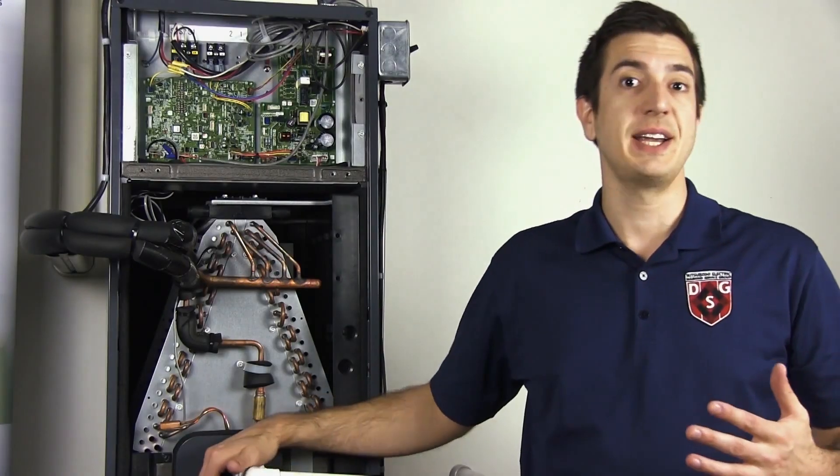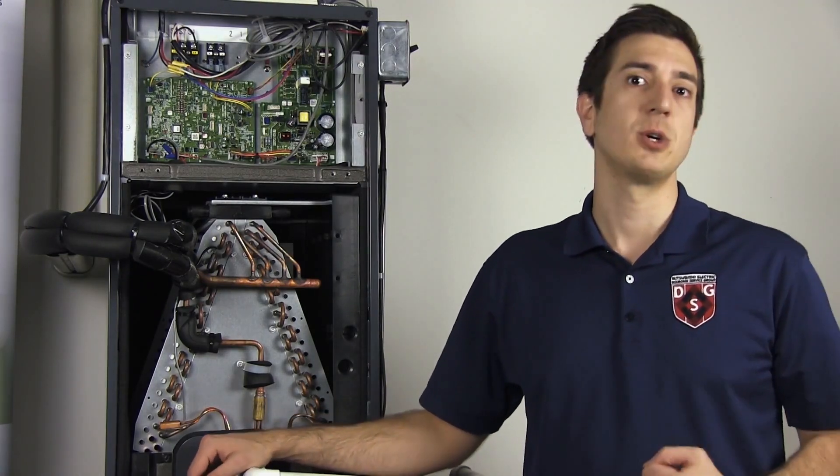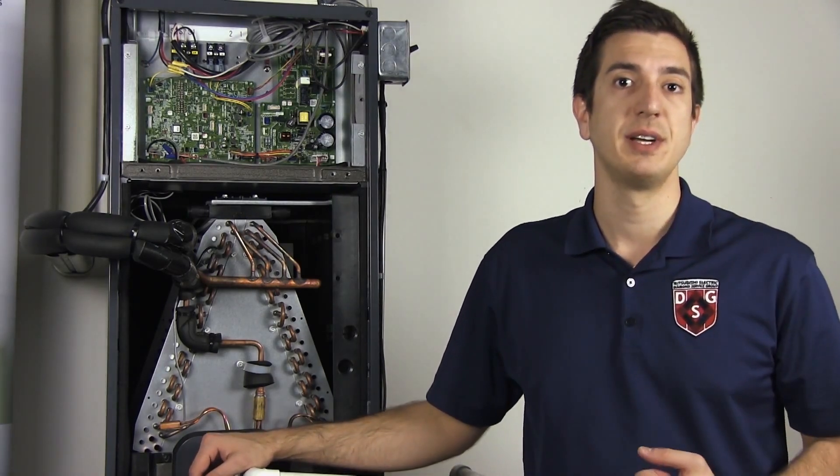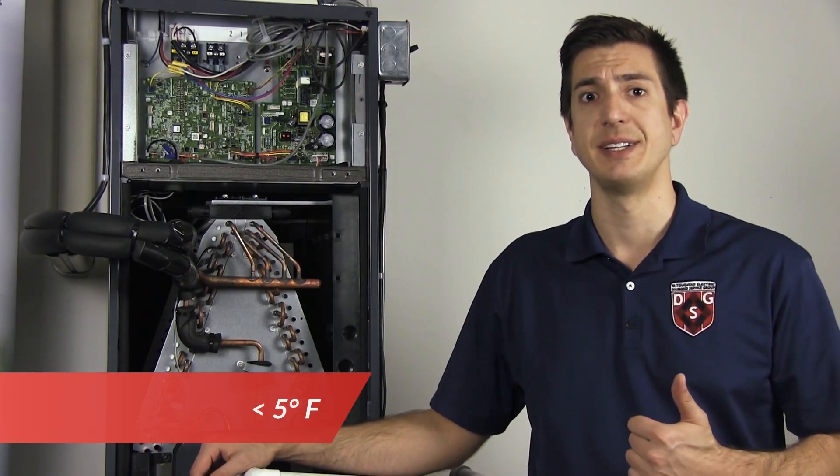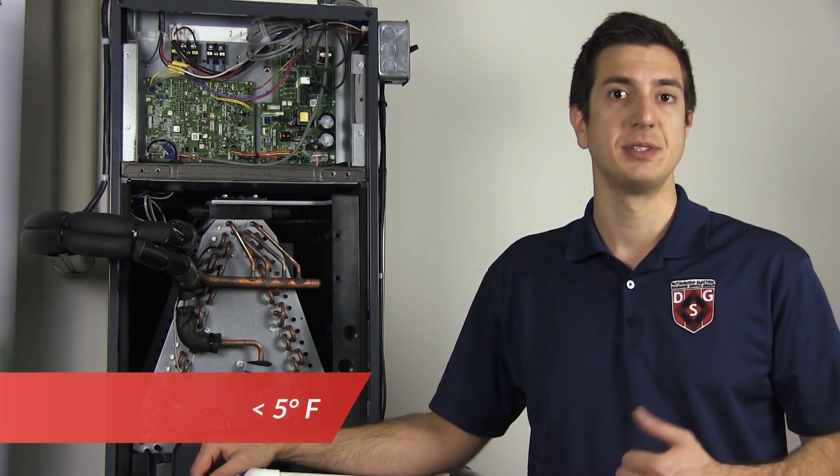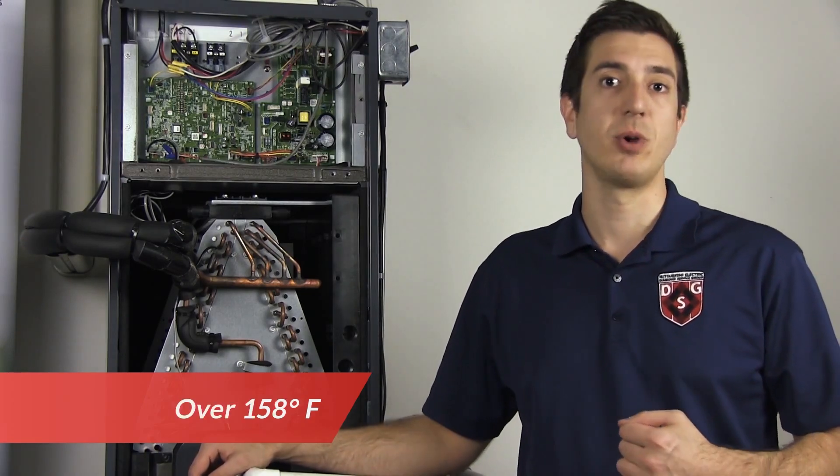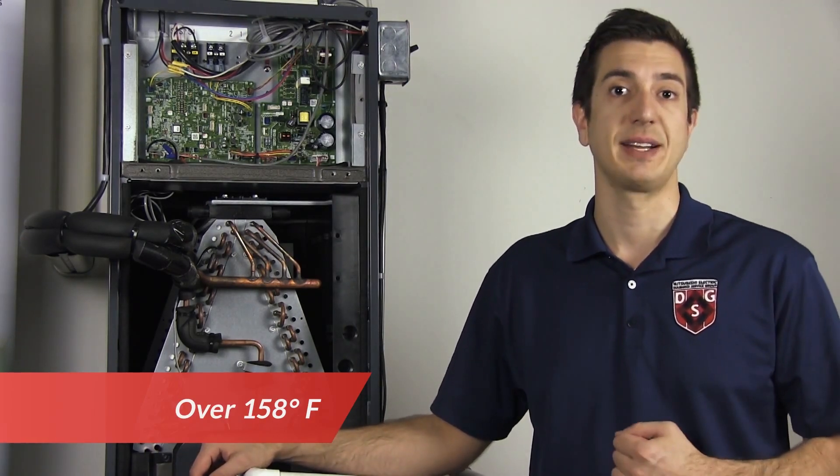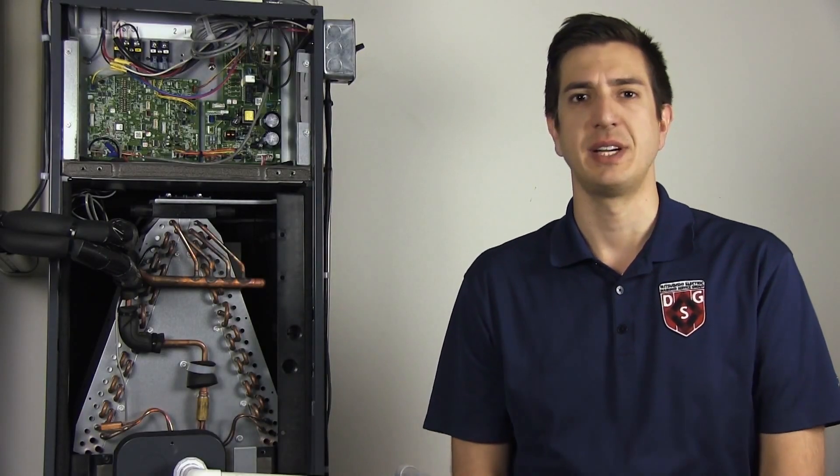So the P6 error means our evaporator coil is either freezing or it's overheating, depending upon which mode we're running it in. In the cooling mode, if our evaporator coil senses less than 5 degrees Fahrenheit during the compressor operation, it'll shut itself down. In the heating mode, if the coil is over 158 degrees Fahrenheit, it'll do the same exact thing.